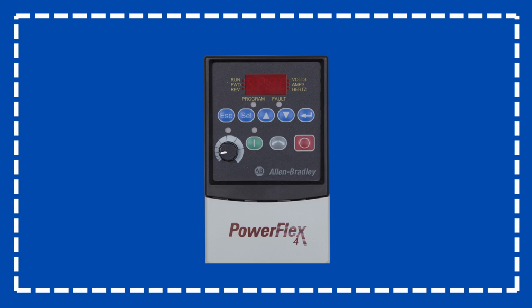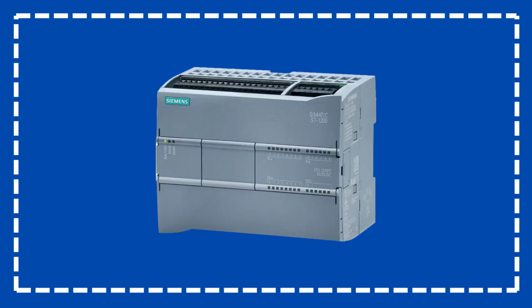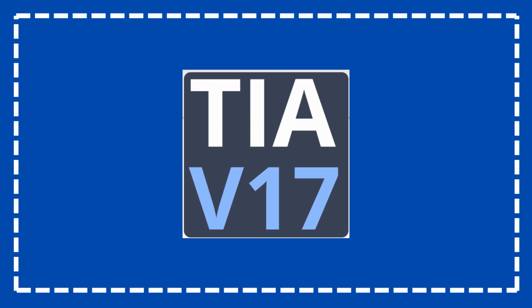In the last practice, we used the PowerFlex 4 by understanding its registers and moving a motor. In this case, we're going to attach a new element, a PLC from the S7-1200 family from Siemens. We're going to use it to communicate and declare a master and a slave between the PowerFlex and the PLC. And by adding some ladder diagrams, we're going to build code that will set up the configuration and the different settings and modes of function in the VFD.